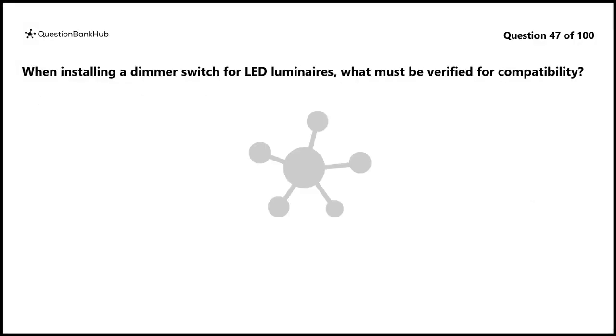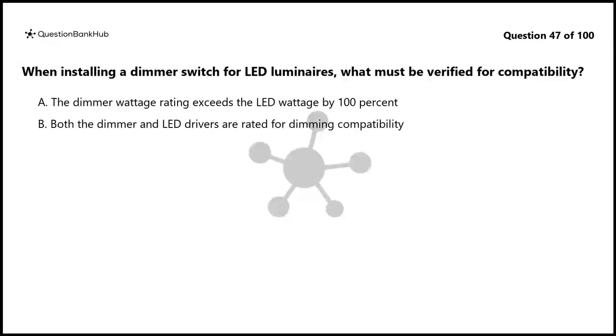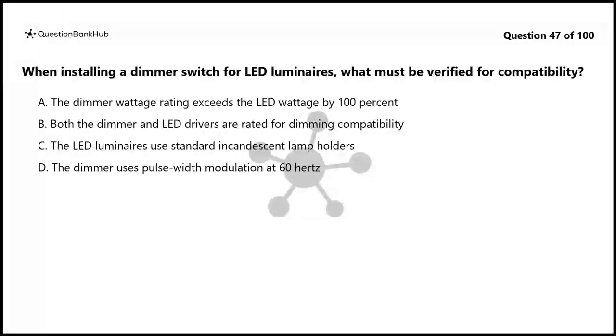Question 47. When installing a dimmer switch for LED luminaires, what must be verified for compatibility? A. The dimmer wattage rating exceeds the LED wattage by 100%. B. Both the dimmer and LED drivers are rated for dimming compatibility. C. The LED luminaires use standard incandescent lamp holders. D. The dimmer uses pulse width modulation at 60 Hz.